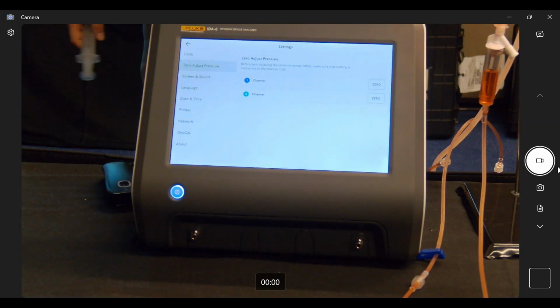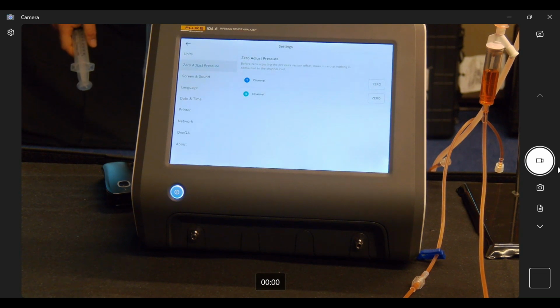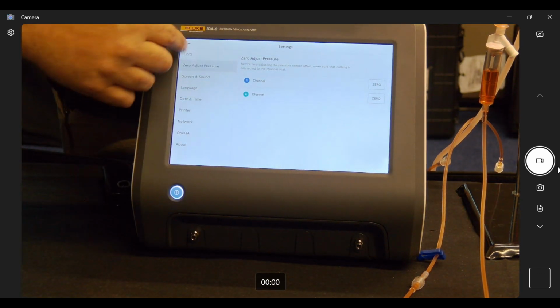So if you're in your hospital and you have to move between a negative pressure room and a positive pressure room, you might have to zero out your pressure transducer. Or if you're in the mountains, like I was yesterday, and come down to sea level, you need to adjust these and zero out the pressure meters every now and again. Not a big deal, so we'll go back in and hit flow.